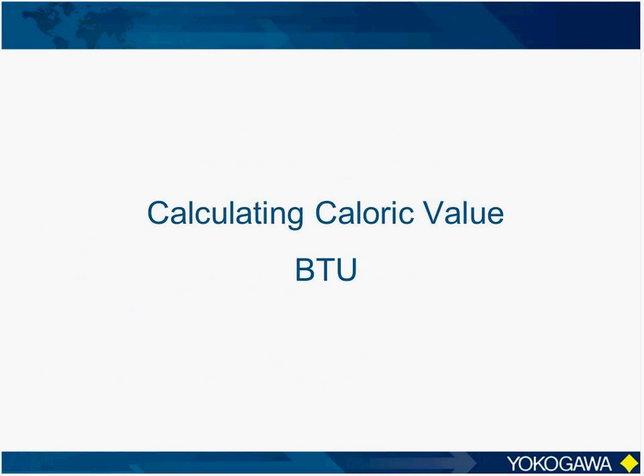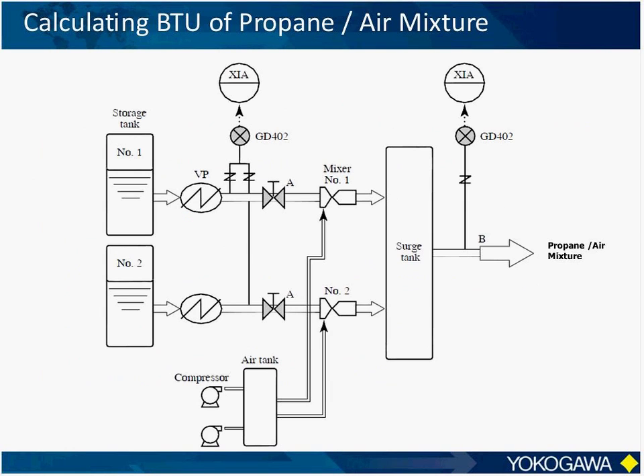Now, the last application we want to discuss is calculating the BTU content of a binary gas stream. Many facilities will have a backup propane supply system for times when their normal natural gas supply is unavailable, or in times of high natural gas prices, it may be more economically advantageous to consume propane rather than natural gas. But since propane has a higher BTU value than natural gas, it must be diluted with air if they want to utilize the same burner settings as those used with their normal natural gas supply.